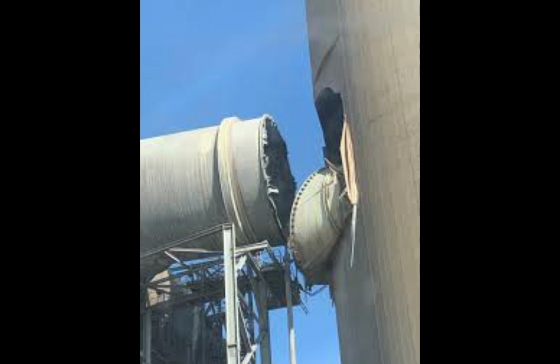This resulted in some of the silica-containing fly ash being carried along to the desulfurization unit. At that stage, hydrated lime sprayed through the emitted gases to chemically bind with the sulfur dioxide and create calcium sulfite was also mixed with the fly ash and subsequently entered the chimney. When combined with heat and fly ash, a hard crust formed along the inner exhausts of the chimney, which over time added too much weight for the structure to support, resulting in damage. The damage to the flue duct and chimney then rendered units 1, 2, and 3 inoperable. This resulted in Kusile and Medupi being considered some of the worst performing units in Eskom's fleet.